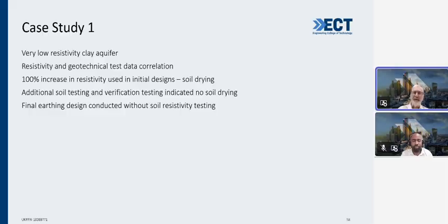I'm going to do the earth resistivity test at 10 o'clock tomorrow morning. So I said, what? He said, no, 10 o'clock in the morning is when I do the test. I said, really? Why didn't you do it in the afternoon? No, mate, we've got to do it in the morning at 10 o'clock. And I found out to my horror that we were right on the beach, and he was doing the earth resistivity tests at high tide, when the resistivity was very low. At 4 o'clock in the afternoon, it was horrendously high resistivity.